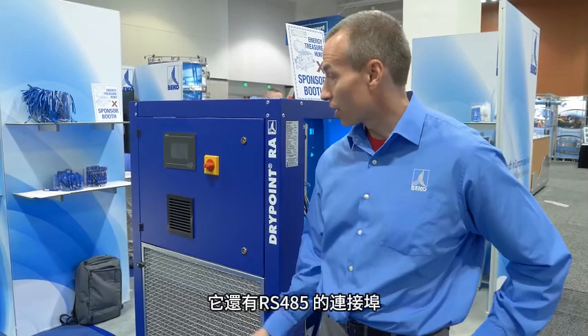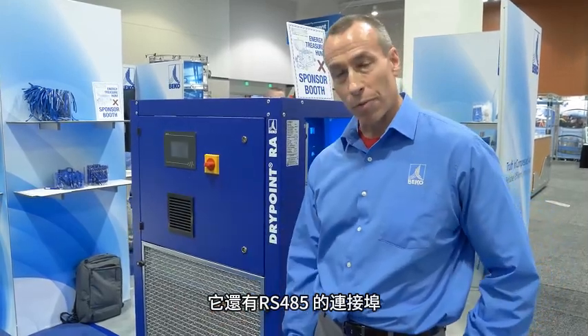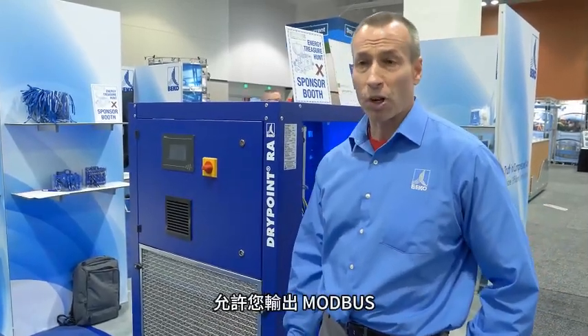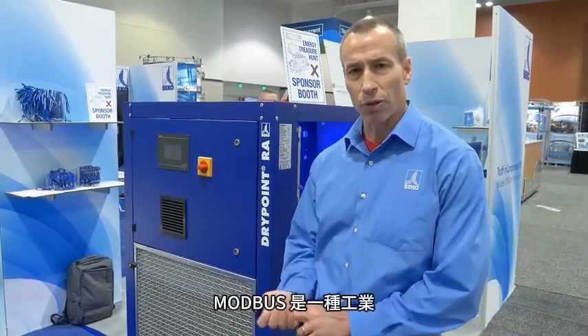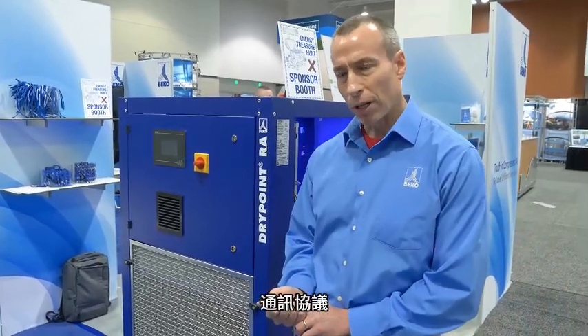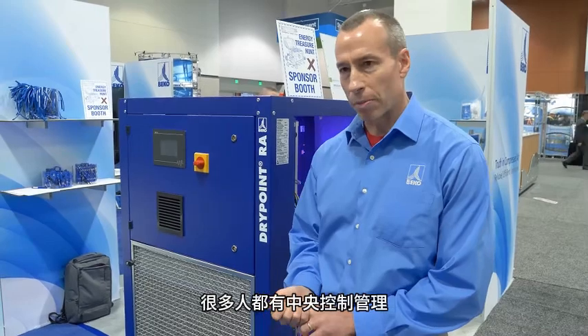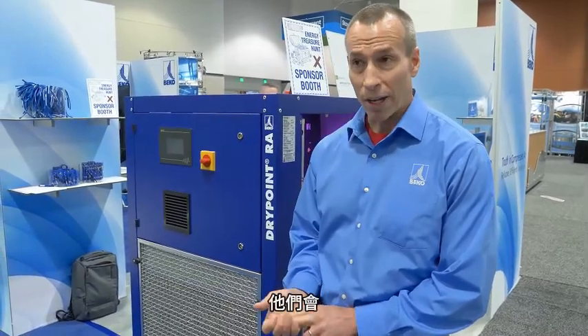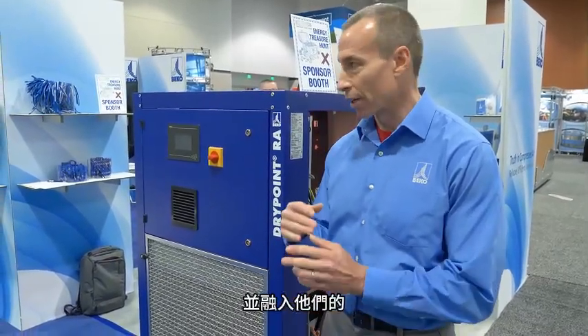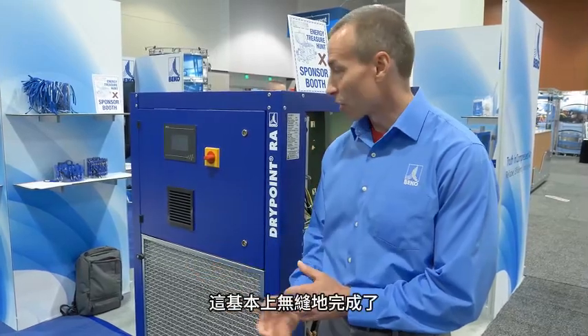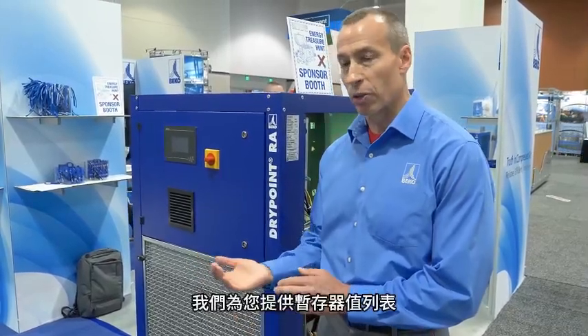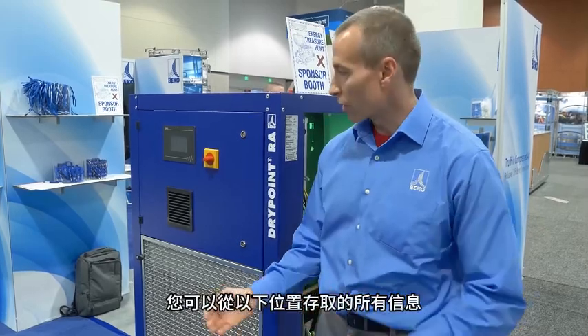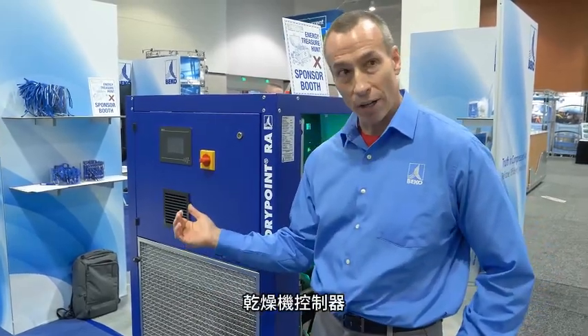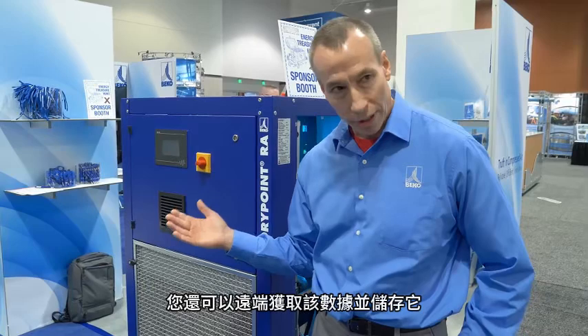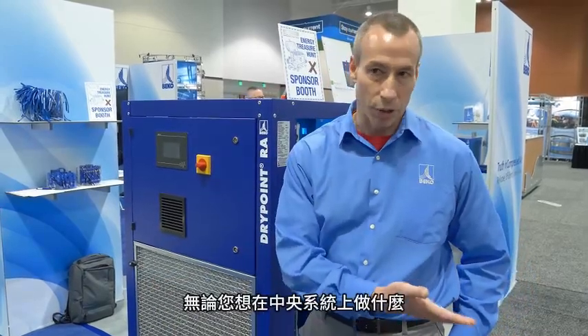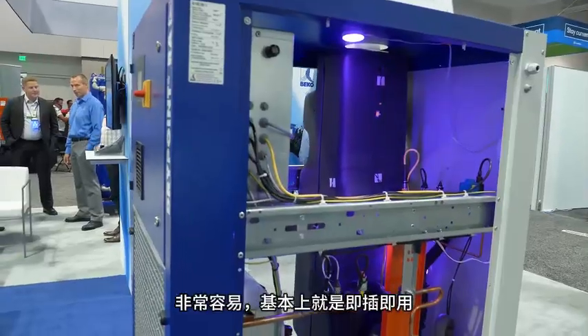There also is a connectivity called an RS-485 port, which allows you to output what's called Modbus. Modbus is an industrial communications protocol. A lot of people who have central building management systems will be familiar with Modbus, and they'll be able to take that Modbus data and integrate it into their central management system. And this does that basically seamlessly. We give you a list of register values, all the information you can access from the controller at the dryer. You can also take that data remotely and store it, monitor it, whatever you want to do on your central system very easily. It's basically a plug and play.